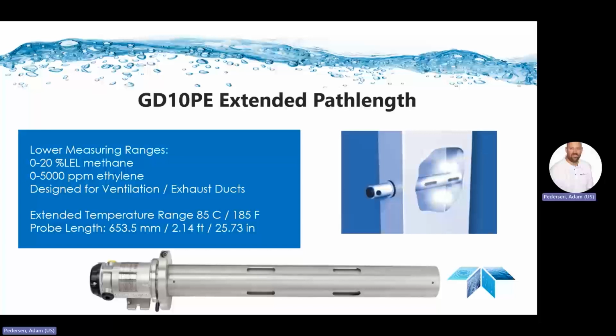The GD10PE is designed to measure hydrocarbons on the enclosure ventilation exhausts of gas turbines and compressors, the only locations where you can guarantee to detect a gas leak in these operations. In applications where you need fast, reliable detection of low gas concentrations, the GD10PE with a range of 0 to 10,000 ppm methane is 5 times more sensitive than conventional point detectors.